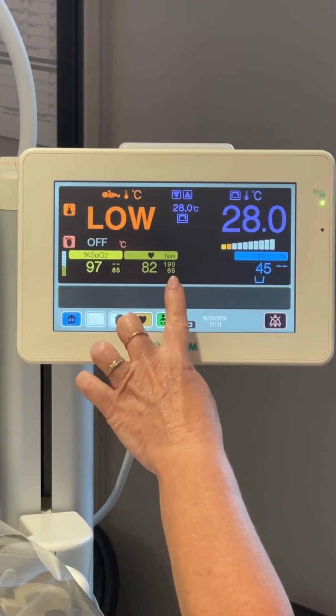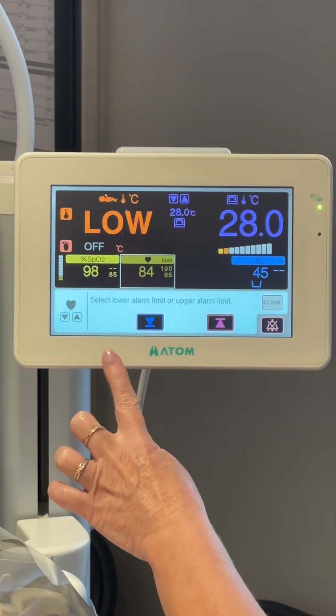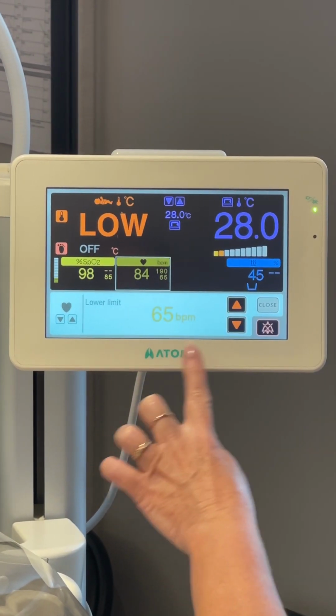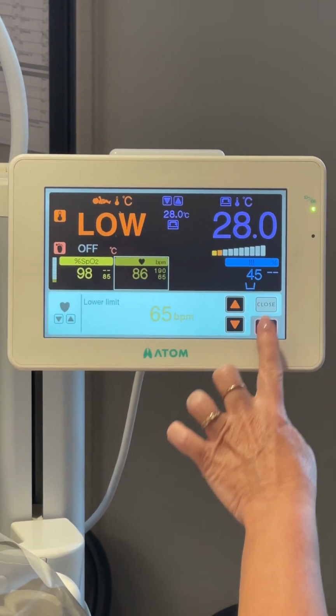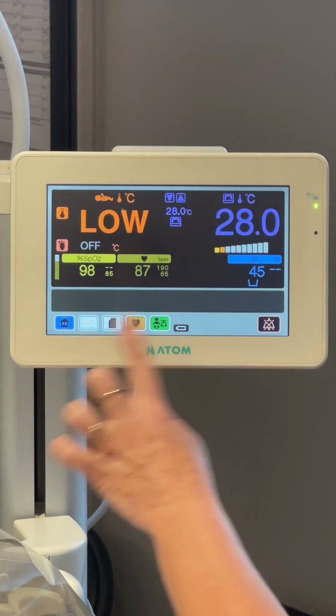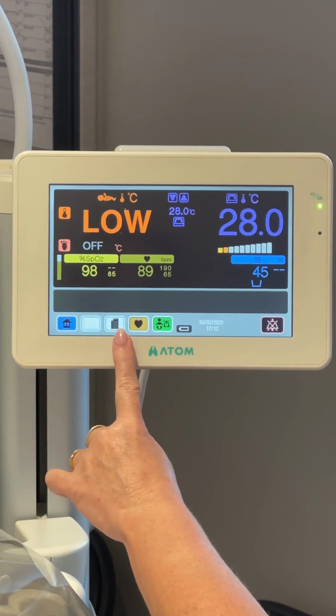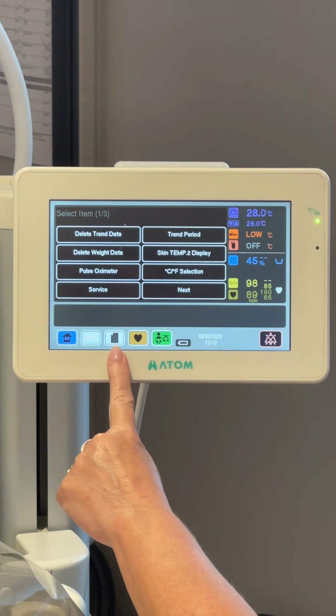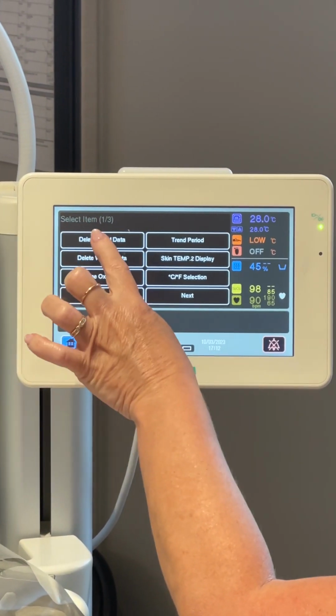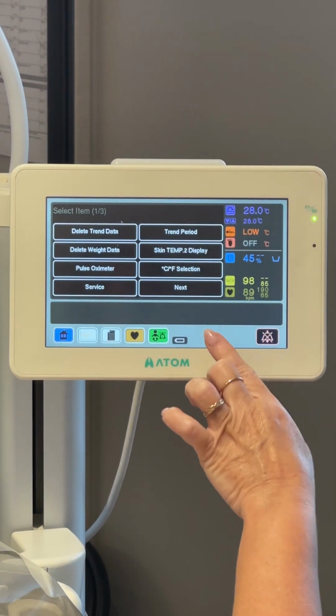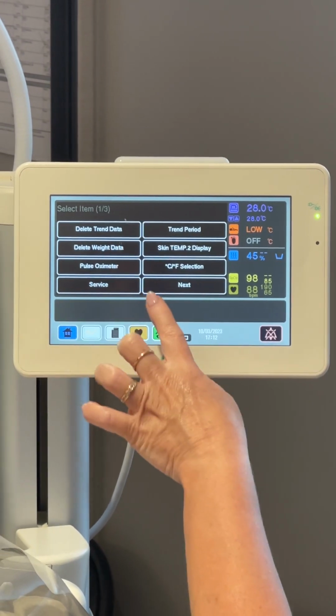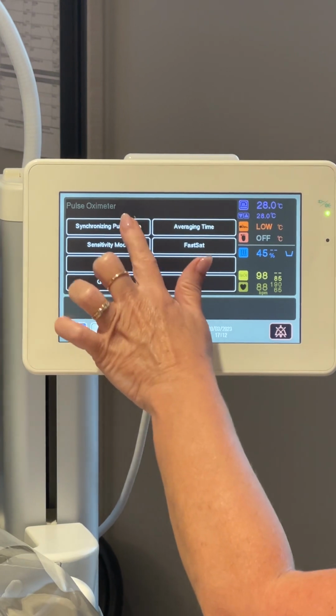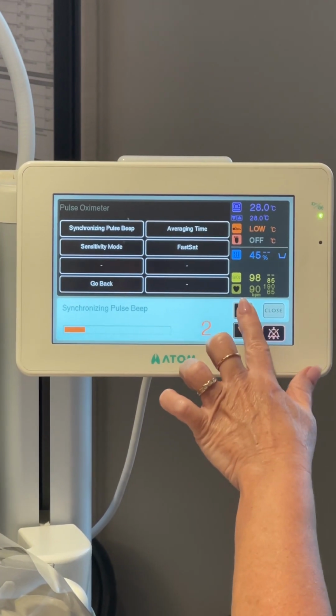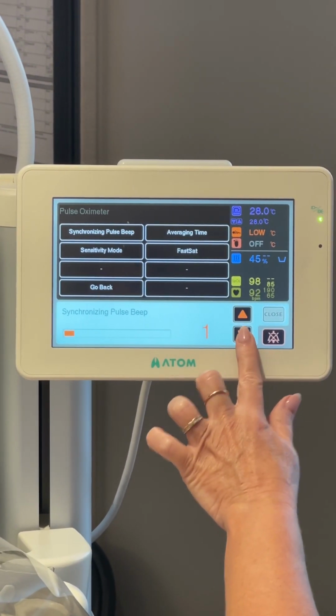And if I did want to change the alarm limit, just touch what you want to change, heart rate, lower, and adjust your set point accordingly. When I'm looking at the menu bar, the third item is a drop-down menu. If I access that drop-down menu, the first 2 items are deleting previous patients' data, like trend and weight data. But the third item is pulse oximeter. If I select pulse oximeter, we can go to synchronizing beat, turn it on, turn it up, or back off.